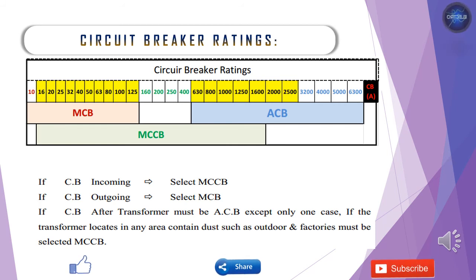Now let's see how we can select a circuit breaker. If you want to select for an outgoing circuit breaker, it's better to select an MCB. For an incomer for a main DB or sub-main DB, depending on the ratings, you can select an MCCB. For high rated currents, it's better to select an ACB — most preferable after the transformer; any panel connected after the transformer can use ACBs.